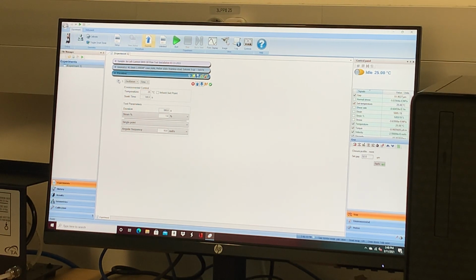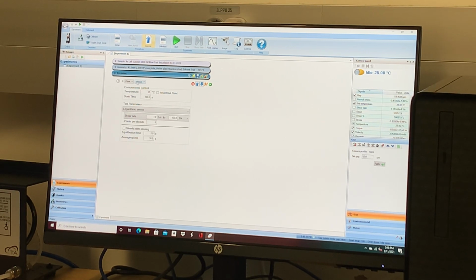Okay, so if we go to procedure, this is the actual procedure we're going to run. Anywhere there's a drop down, you can select the test. So you have a choice of oscillation, flow, step. We're going to do a flow test, and we'll run an oscillation too, but I'll go over these other guys real quick. Step would be a test like creep or stress relaxation or stress growth. These are types of tests where you're putting torque on a sample and then you're just seeing what it does. There's no oscillation, you just put some torque on and see how the sample reacts. Those are those types of tests, okay?